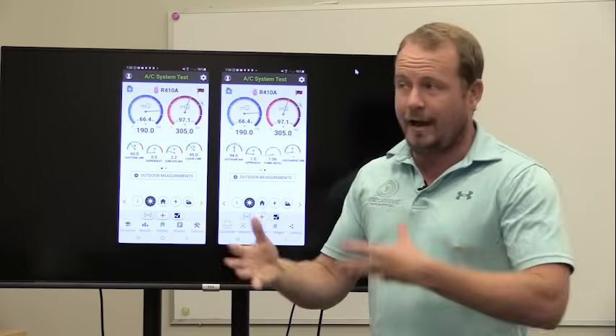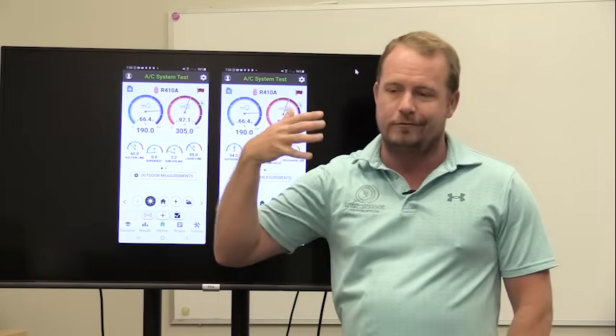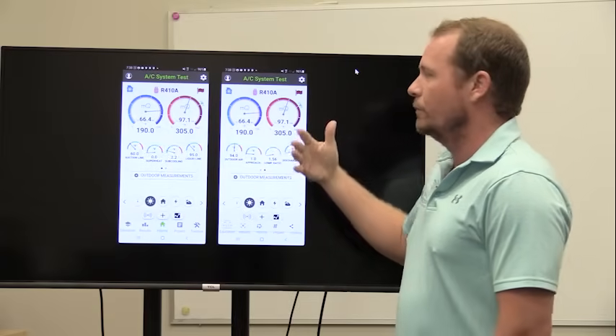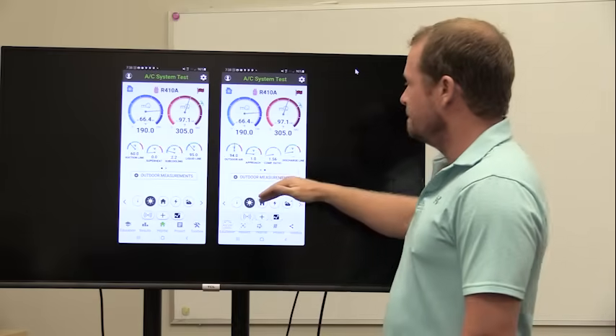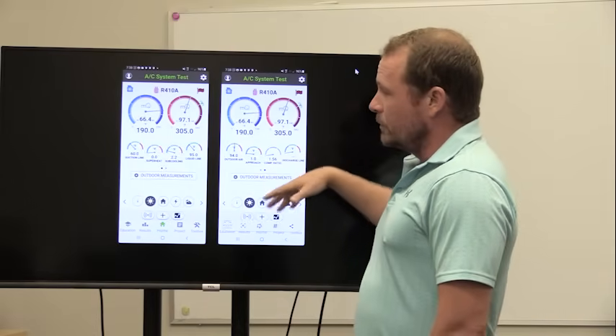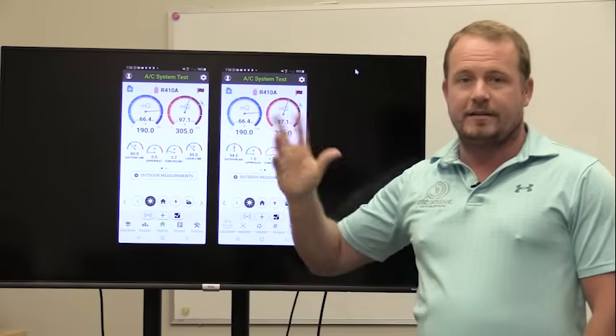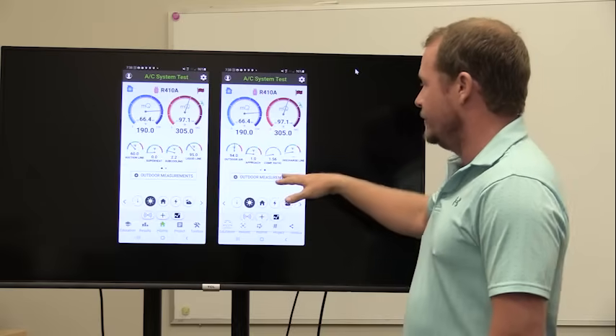MeasureQuick does that for you. So you don't have to do that additional math. But just keep in mind that it isn't going to be true. And it's not going to be exact if you're measuring on your liquid line because your liquid line pressure is going to be slightly lower than your discharge pressure. But what you will notice is if it's running properly, 2.3 to 2.7 is going to be sort of typical when you start to drop below two, that's really when you have an indication of poor compression. And so that tells us we've got a compression issue.